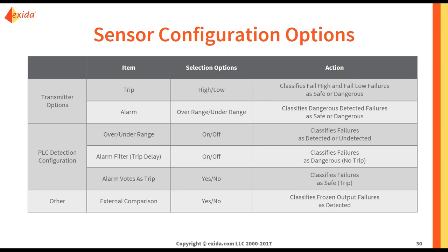The last option is external comparison. If you have a separate transmitter signaling a separate PLC, you can compare the outputs of the transmitters to see if something is wrong with the transmitter in your safety instrumented function. In this case, you might actually be able to detect frozen output failures. Usually you would not know it is frozen because it is in the healthy range. However, if the other transmitter you are comparing to is showing different values, it might indicate a frozen output failure, and you can count that as detected.